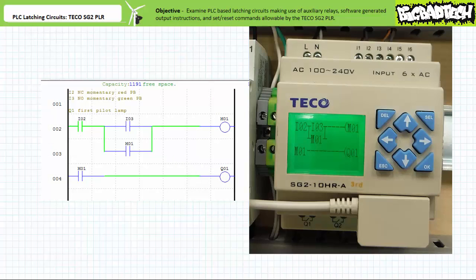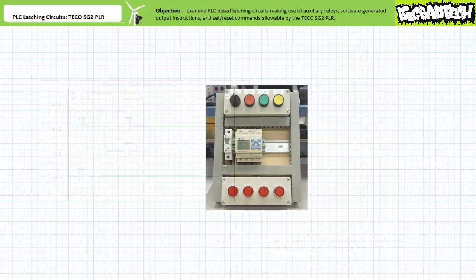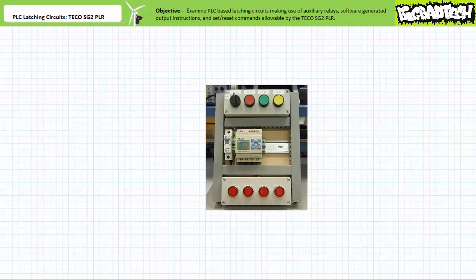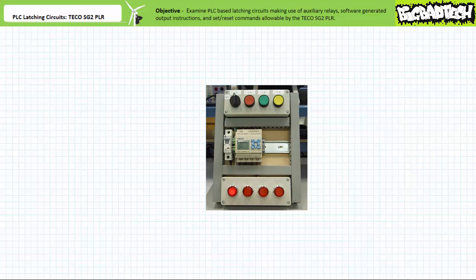When the program is downloaded to a target device, note the subtle formatting difference between the programming software and that employed by the actual device. When the system is placed into operation, note that when an operator presses and releases the normally open green pushbutton on input 3, the first pilot light turns on and stays on as expected. When an operator presses and releases the normally closed red pushbutton on input 2, the holding circuit is broken and the first pilot light turns off and stays off as expected.